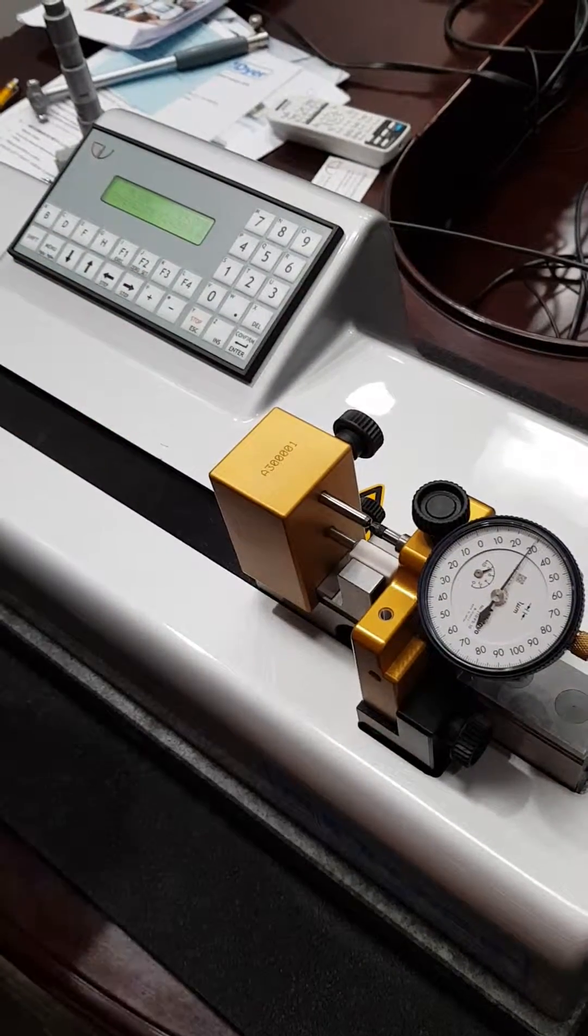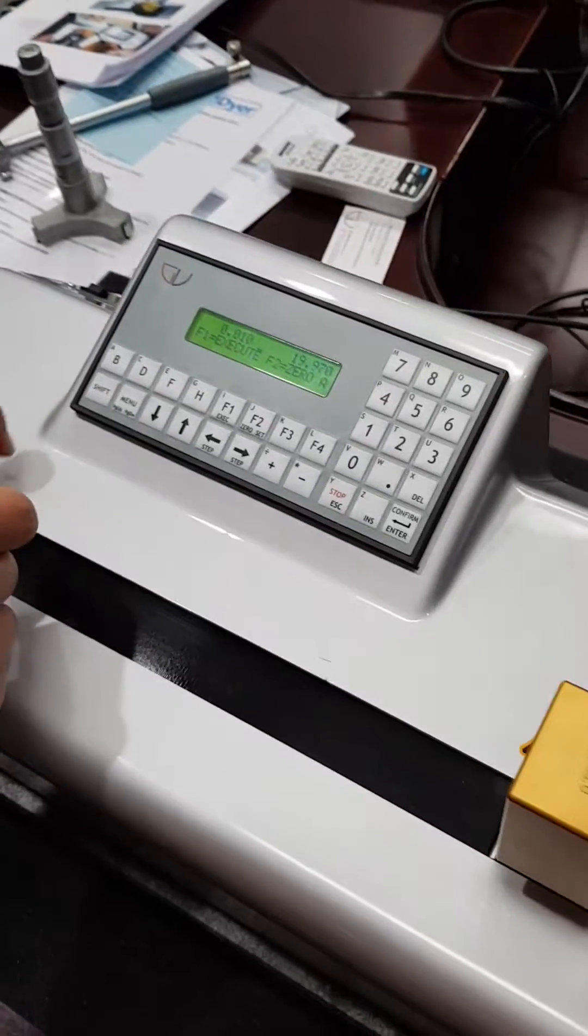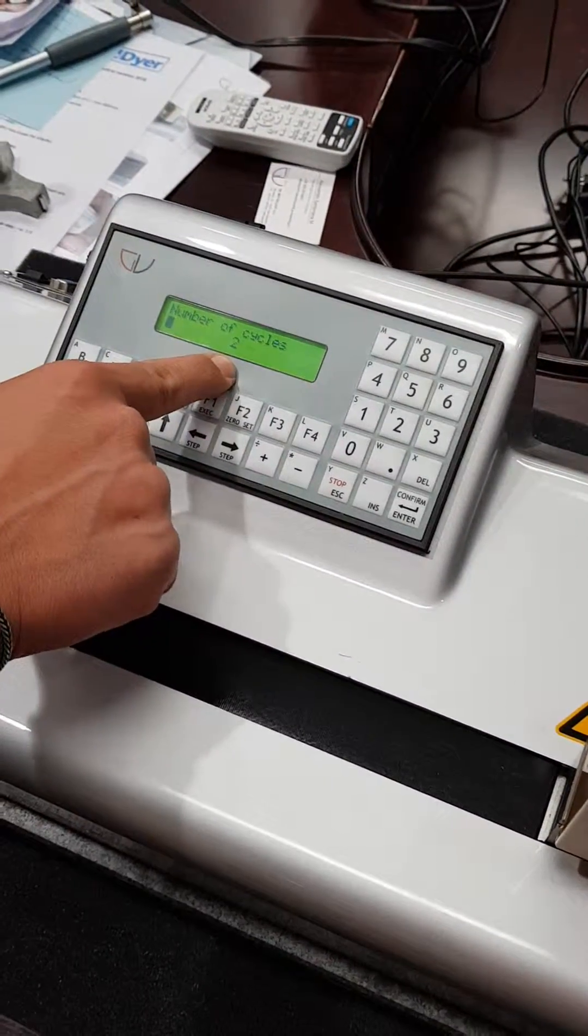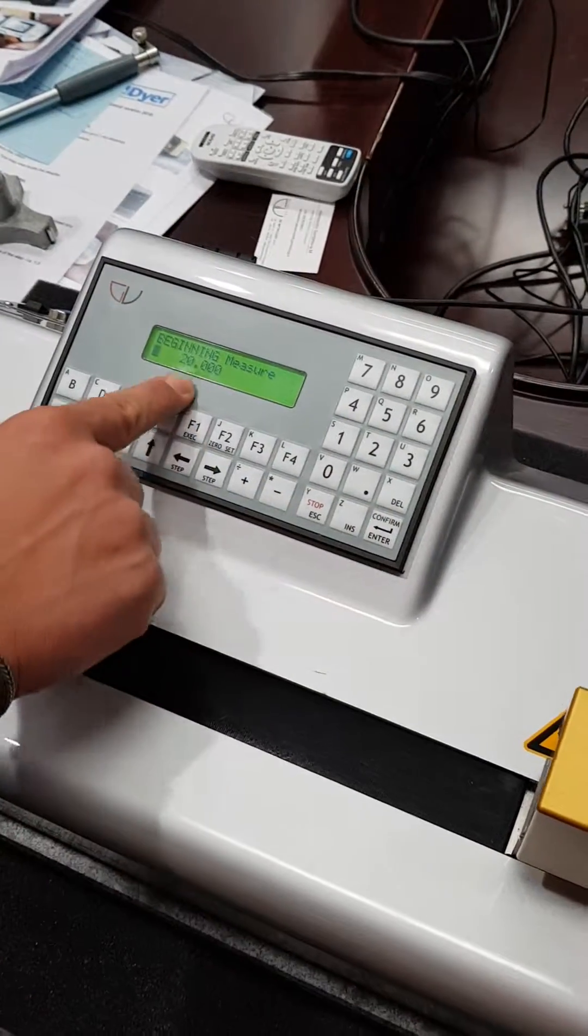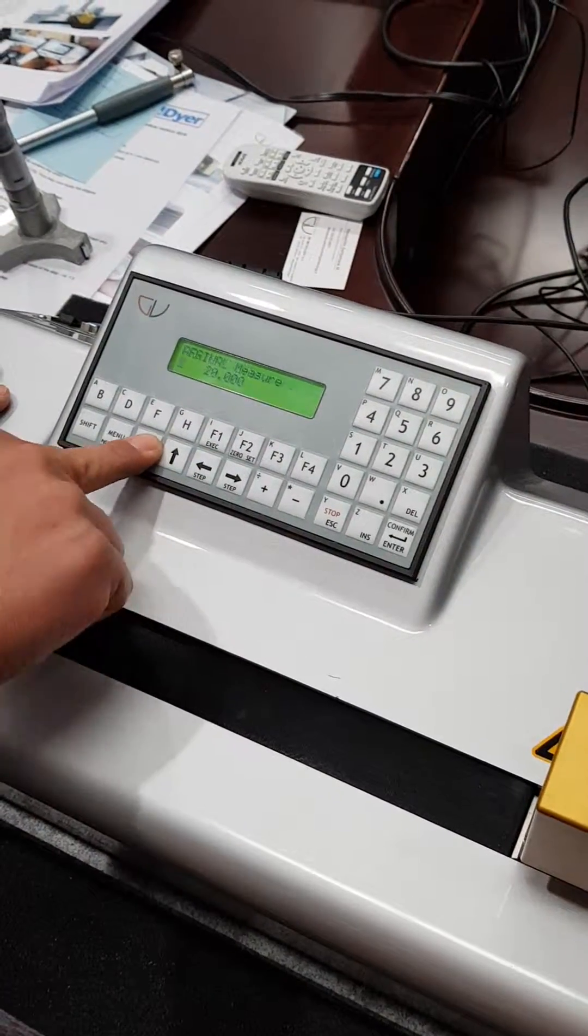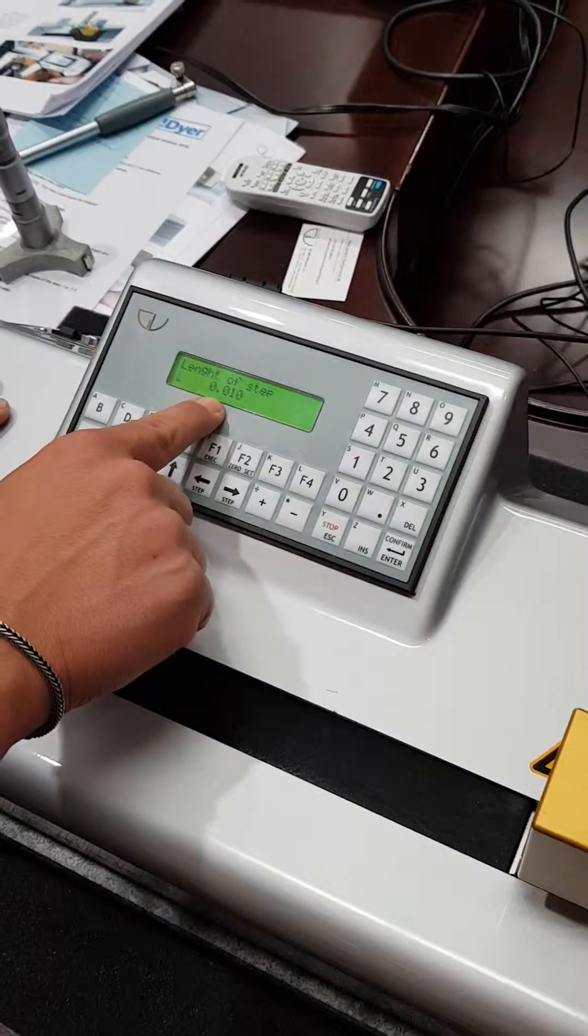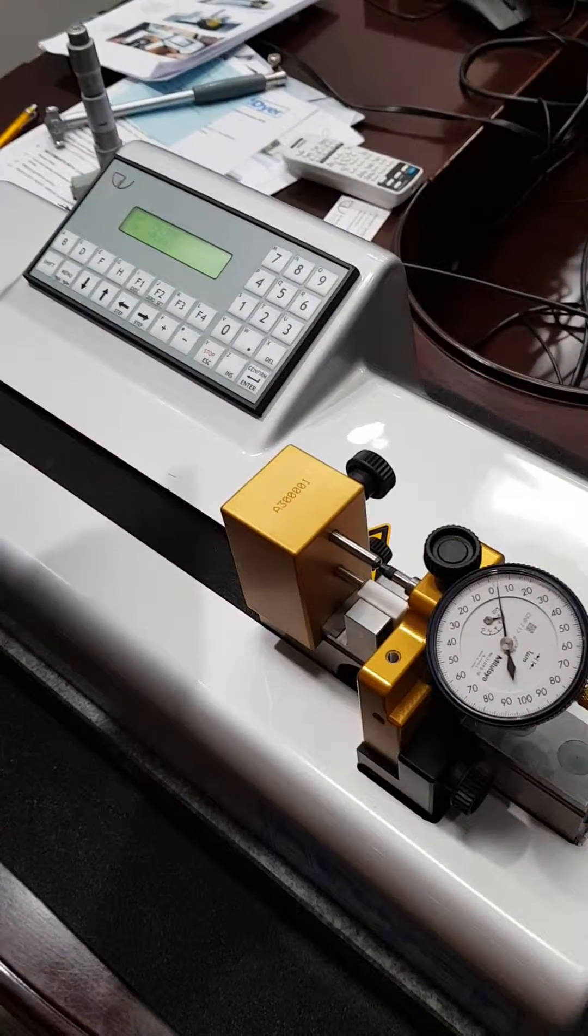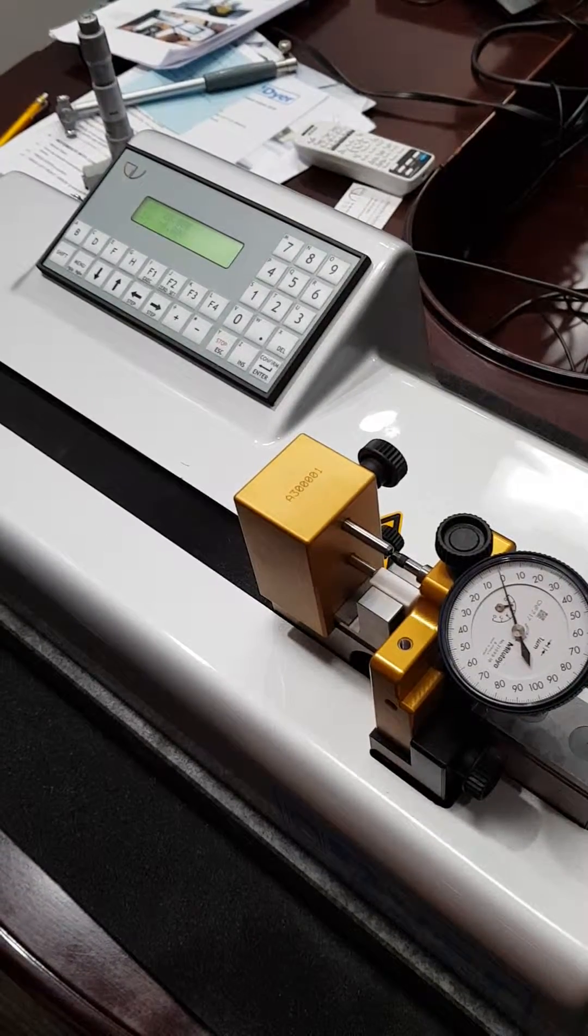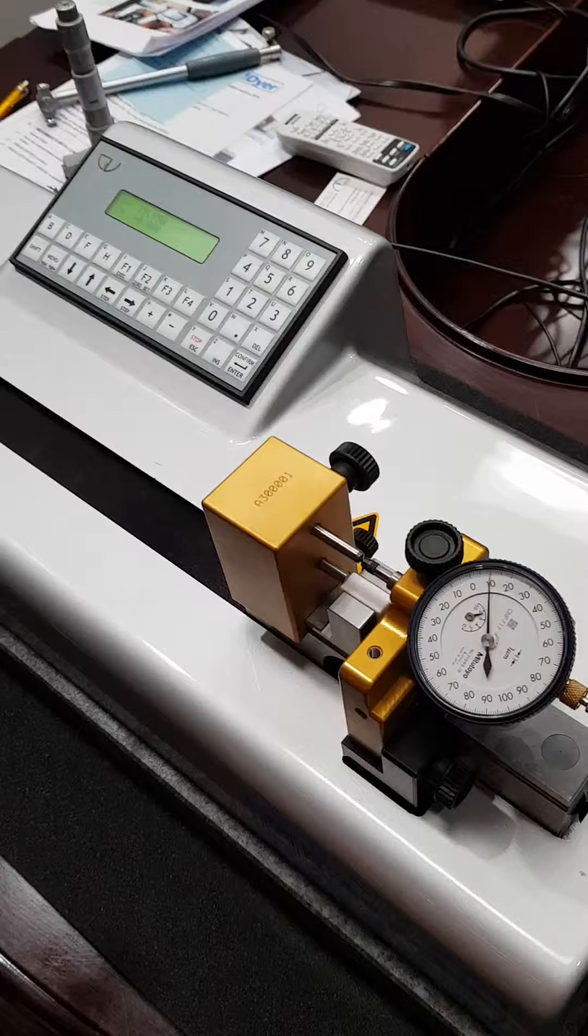The same thing we can do with automatic steps. Pressing shift and right arrow, I open the program. I decide to have one cycle. Beginning measure was 20, arrival let's say 19.9, with 10 micron step. With escape I'm going to enable the cycle, and this is going to happen every three seconds. I have the step I said before.